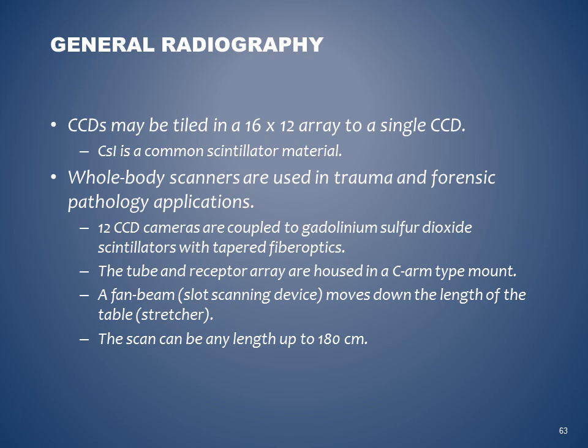General radiography: CCDs may be tiled in a 16 by 12 array to a single CCD. CsI is a common scintillator material. Again, hint, hint, you might need to know that CsI is a common scintillator material. Whole body scanners are used in trauma and forensic pathology applications. 12 CCD cameras are coupled to a gadolinium oxysulfide scintillator that is tapered with fiber optics. The tube and receptor array are housed in a C-arm type mount. The fan beam, slot scanning device, moves down the length of the table or stretcher. The scan can be any length up to 180 centimeters.